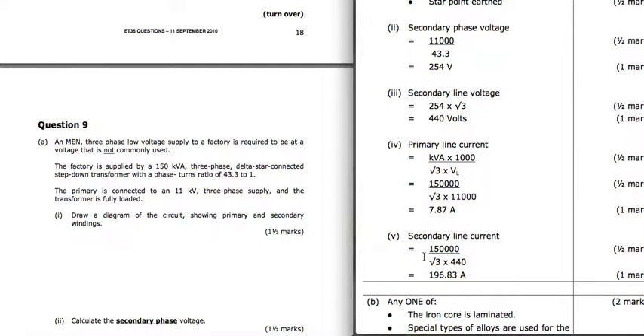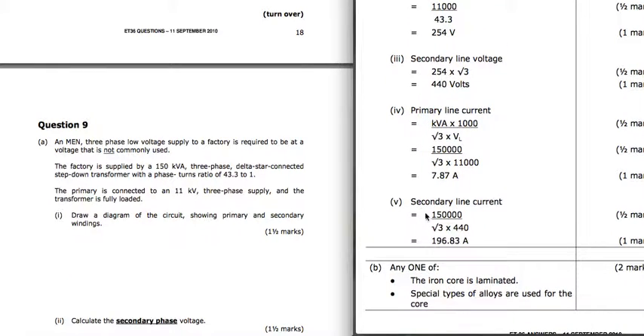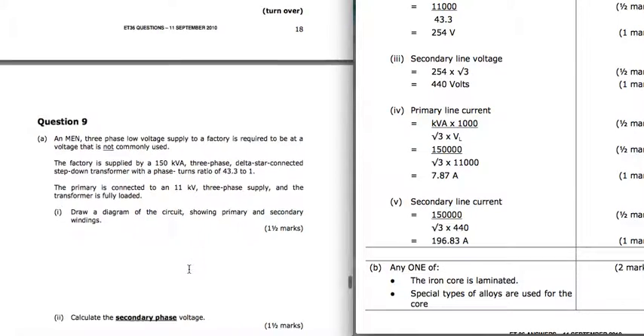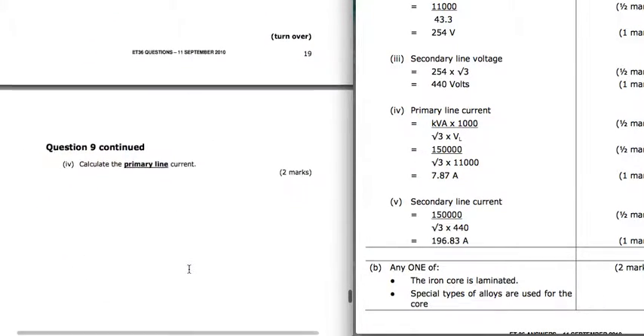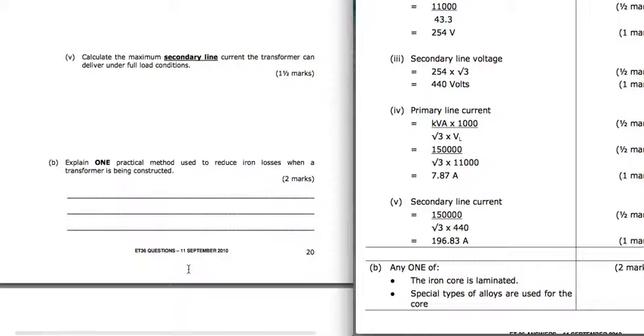The secondary line current is going to be a similar calculation. The power of the primary and the secondary, or the kVA, is exactly the same, 150 kVA. So 150,000 divided by √3. The only difference now is our 440 volts that we've calculated up here, our line voltage, 440, and that gives us 196.83 amps. So a much higher current in the secondary.